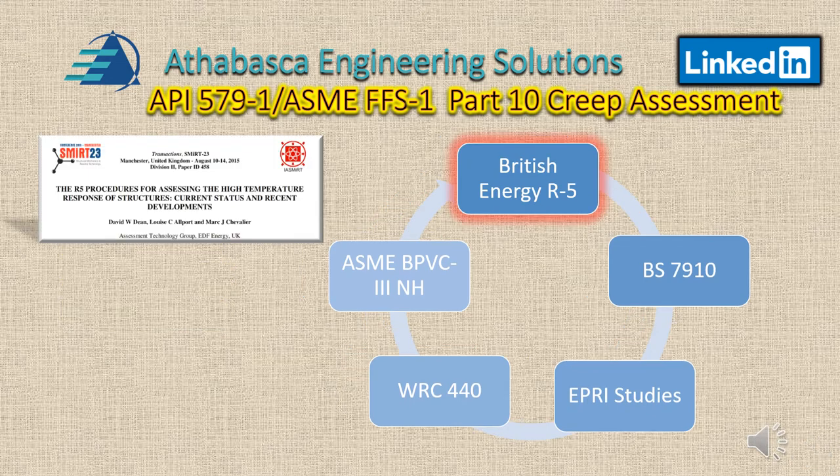The British energy industry uses the R5 procedures as a method to assess the integrity of nuclear and conventional plants operating at high temperatures. They routinely use these standards for assessment of metallic components — for example, for advanced gas-cooled reactors that typically operate in the 470 to 650 degrees centigrade range. This is an international procedure that has been developed over the years with cooperation from several countries.